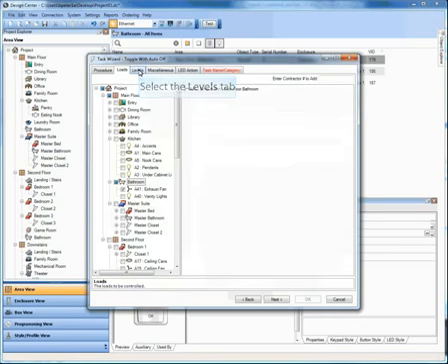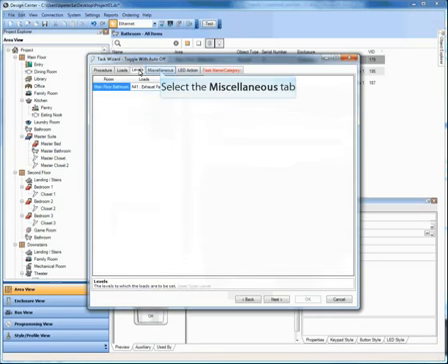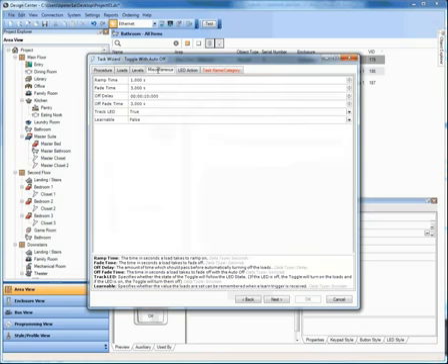I check the box. Go to my levels tab. It's going to be 100%. It's a relay load, so it's going to be 100% anyway. I go to my miscellaneous tab and I'm going to choose a 0 and a 0 for the fade and ramp time. Since this is a relay load, I don't need any of those. And in this next field, the off delay, I have hours, minutes, seconds, and milliseconds in these four sections left to right.